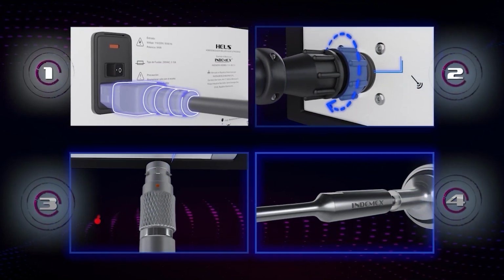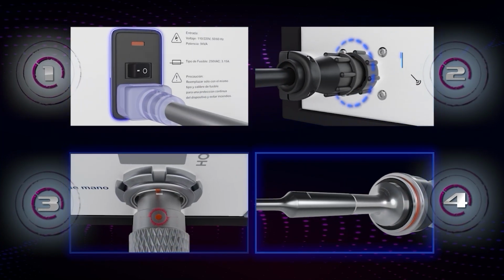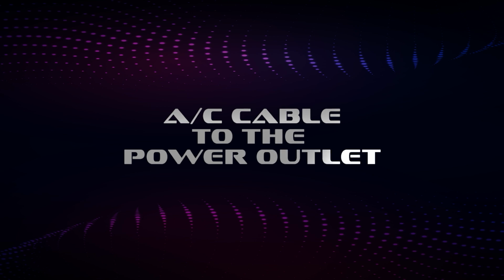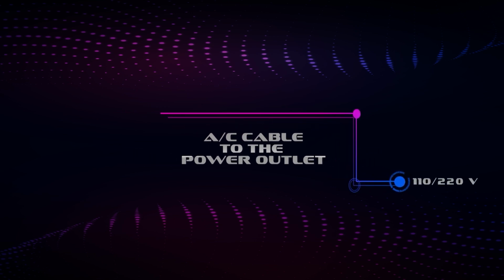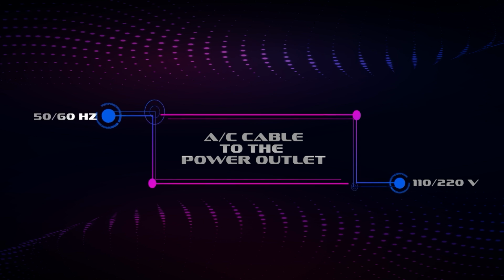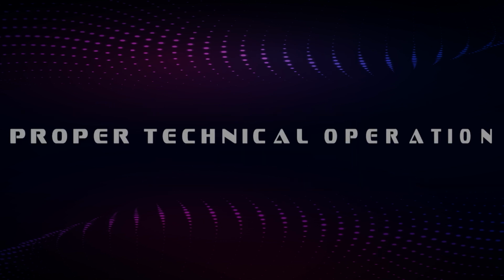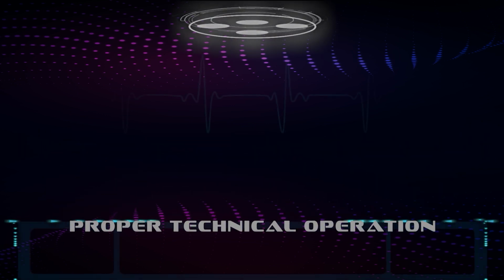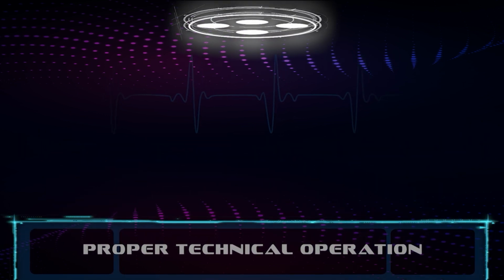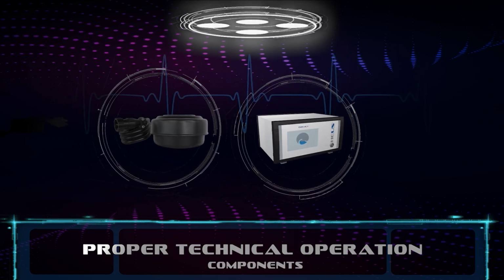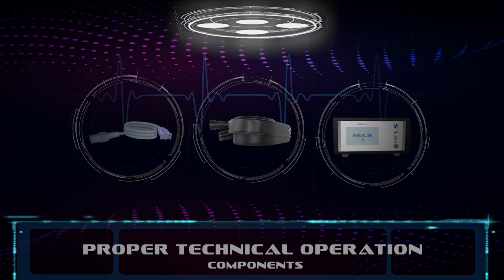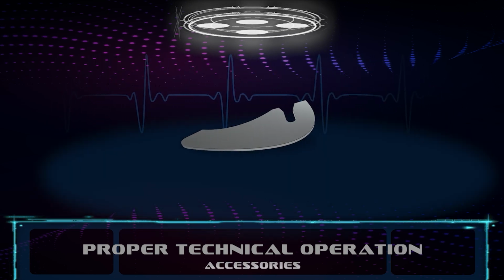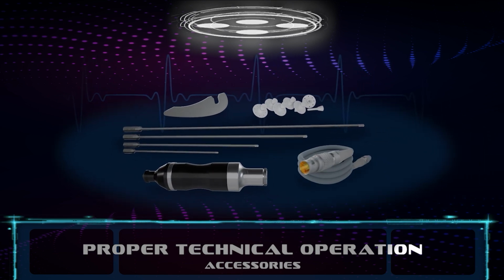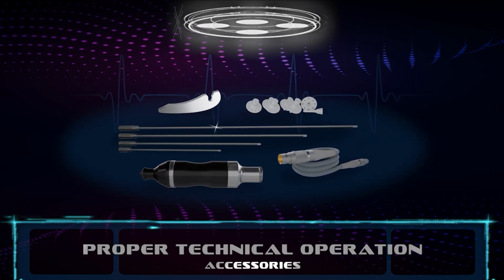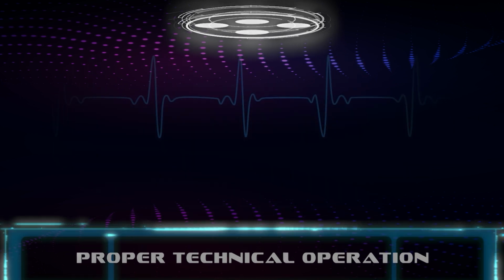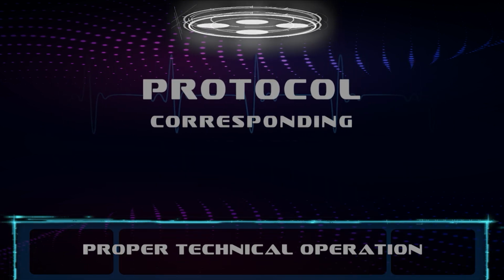Once the 4 assembly steps are completed, we can proceed to connect the end of the AC cable to the power outlet on the wall, from 110 up to 220 volts and from 50 up to 60 Hz. Proper technical operation. It should be noted that for the HELS device to enter the operating room, its components, console, pedal, and AC cable must be cleaned according to protocols. Accessories such as wrench, sonotrodes, ports, handpiece, and handpiece cable must be disinfected and sterilized in advance and entered into the operating room under the corresponding protocol.